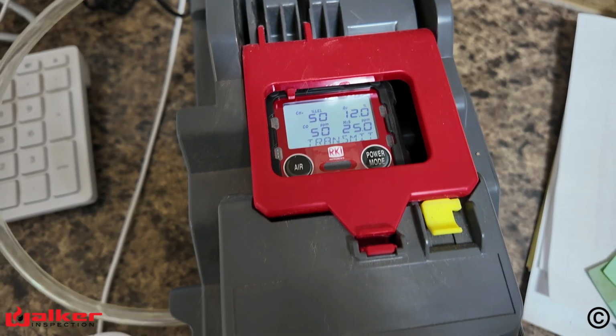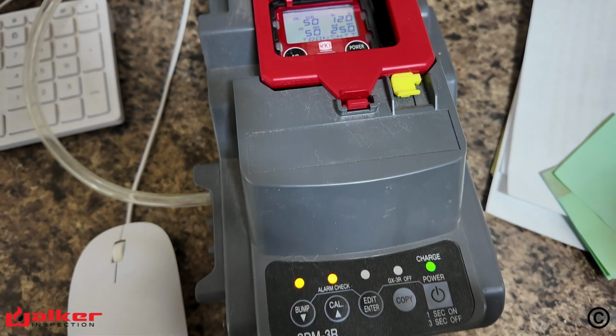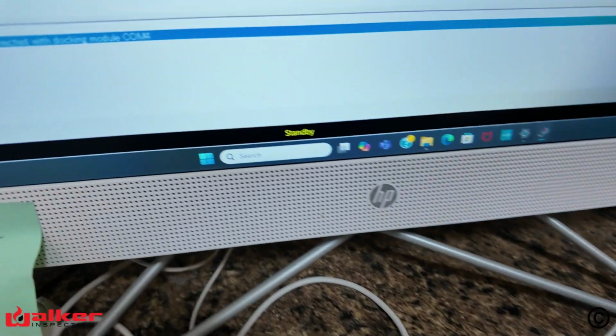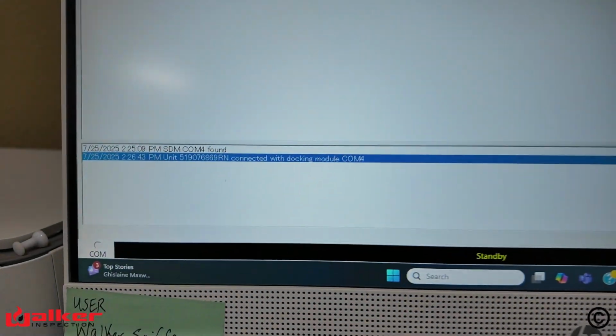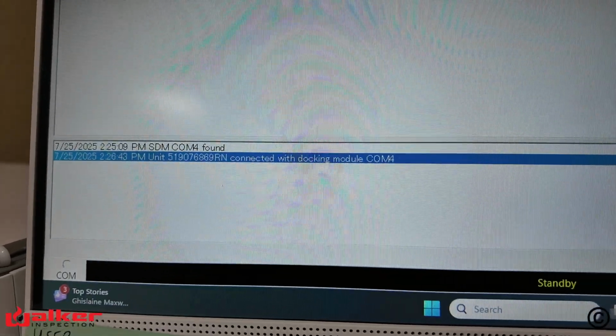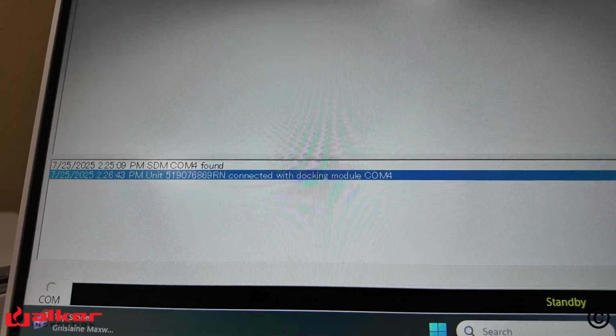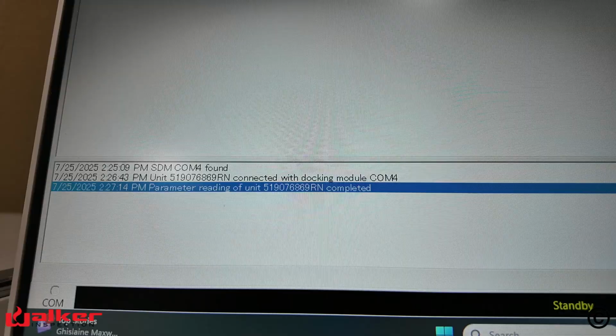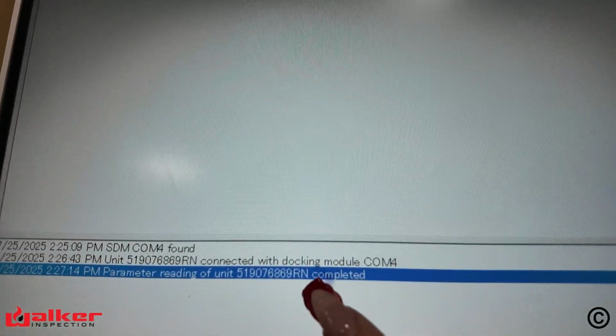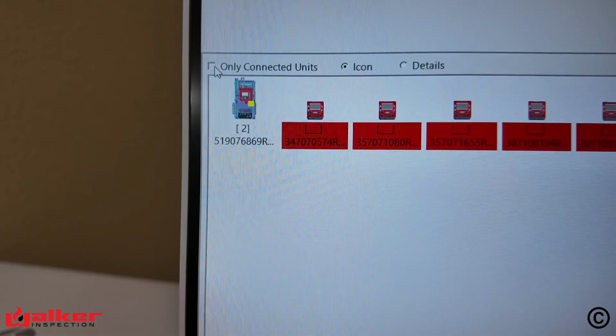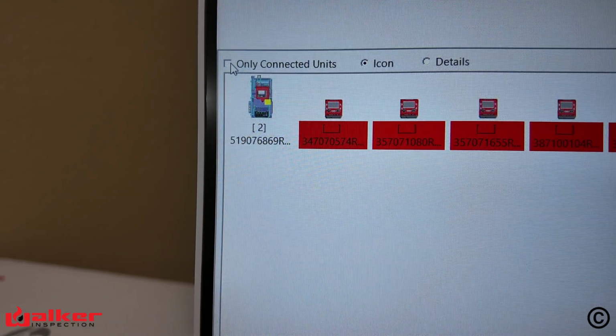Now that the monitor is in and the red bracket is down, the monitor will automatically turn on and transmit the monitor to the app. Before you're able to calibrate or bump test the monitor, it needs to be fully connected to the system. At the bottom, you'll see the monitor found, but you need to wait until it says Monitor Completed as seen here. First, we're going to show you how to do a full calibration of the monitor.